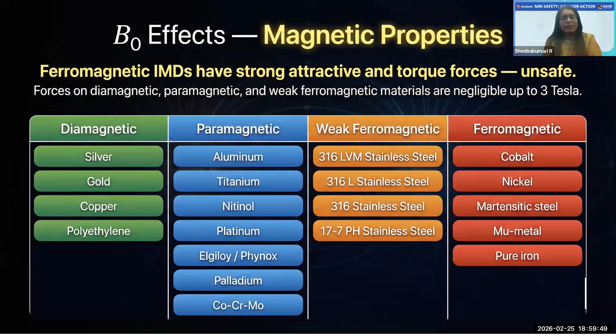These devices are unsafe to scan in MR. Whereas modern implants made of titanium, nitinol, platinum alloy, phynox, palladium, cobalt-chromium-molybdenum have negligible attractive forces up to 3 Tesla. Another concern is whether these implants are fixed or free. If the implant is fixed to the body, it will be anchored by tissue holding forces. If they are encapsulated by fibrous tissue or surgically fixed, they do not move in the MRI, because the magnetic force never exceeds the tissue holding force needed to move these devices.